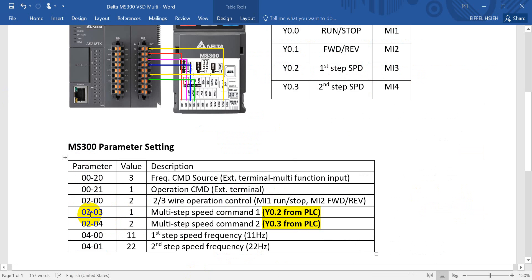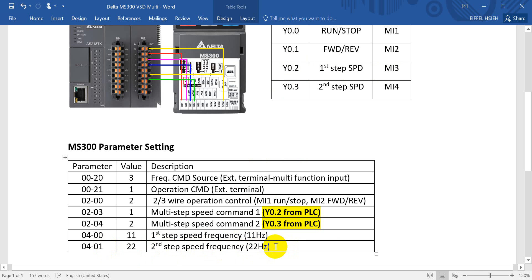Parameter 02-03 is set to 1, meaning multi-speed command 1, and parameter 02-04 is set to 2, meaning multi-speed command 2. These two signals come from PLC Y0.2 and Y0.3. In today's example, the first step speed frequency is 11 Hz and the second step speed is 22 Hz.